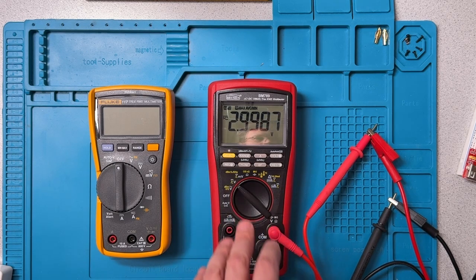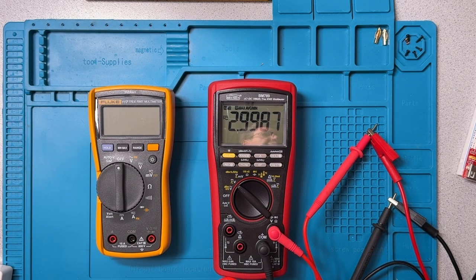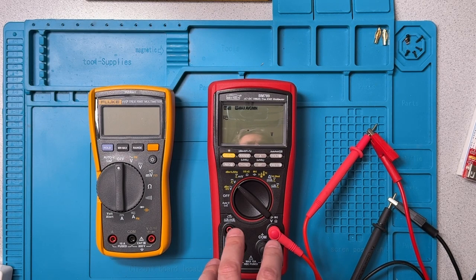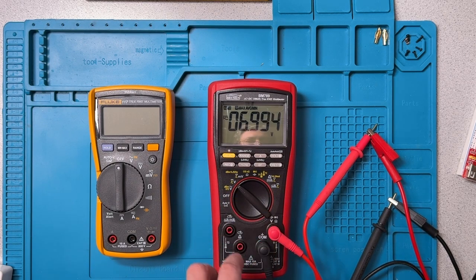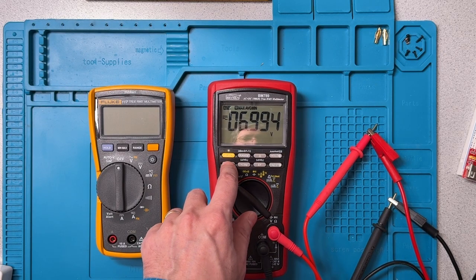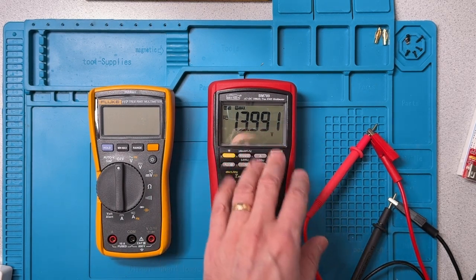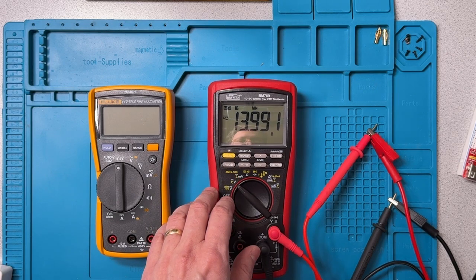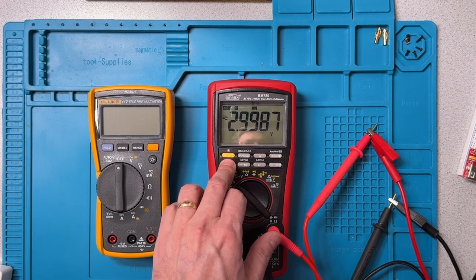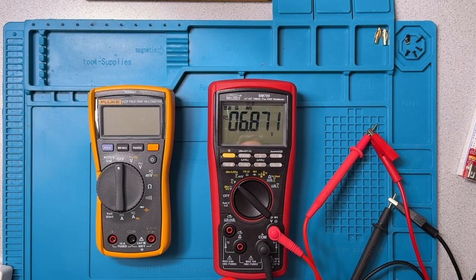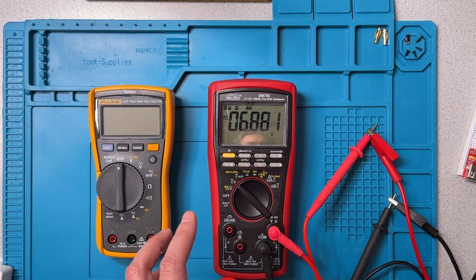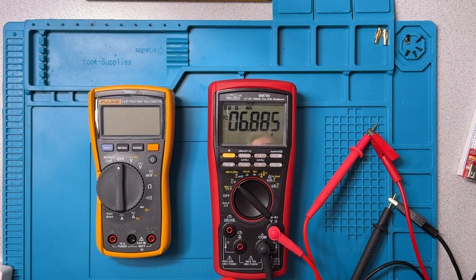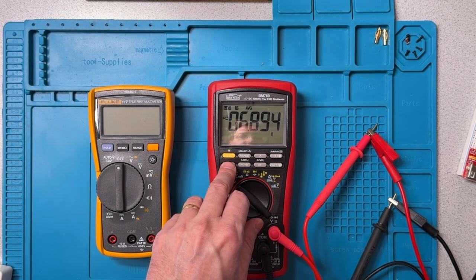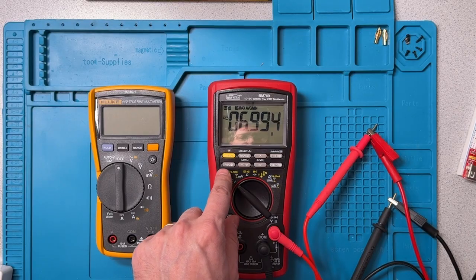Now, it beeps every time it locks into a new value. And the other thing is, once it's been doing these things, I can press this button to show me what the maximum was over this time period, so 13.99 volts, the minimum, which was 2.99 volts, and then the average voltage over that time period. So if there's some changing voltages going on and I want to catch what the maximum was and what the minimum was, and maybe I'm interested in that average voltage, that's what this recording max min average mode can do.